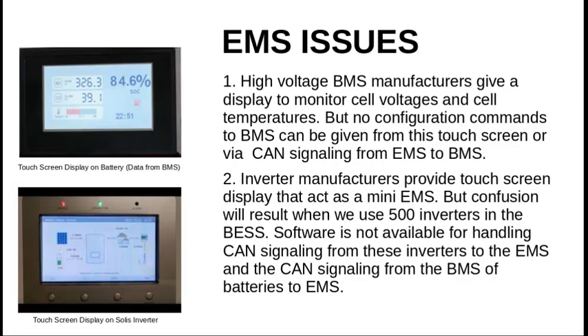EMS issues. Point 1. The high voltage BMS manufacturers give a touchscreen display to monitor cell voltages and cell temperatures, but no configuration commands to the BMS can be given from this touchscreen or even via CAN signaling from the EMS to BMS. Point number 2. The inverter manufacturers provide a touchscreen display that acts as a mini EMS, but confusion will result when we use 500 inverters in the BESS. Software is not available for handling CAN signaling from these many inverters to the EMS and the CAN signaling from the BMS of the batteries to the EMS. So these are the software issues for the EMS.